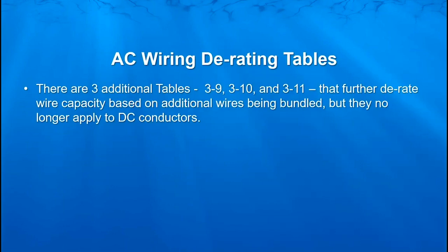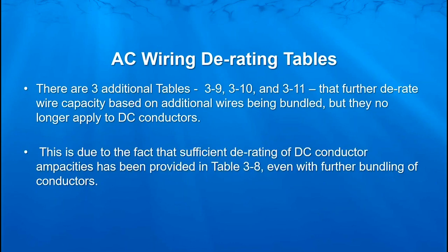There are three additional tables which you don't necessarily have to worry about, just to understand that they're there. They further derate the current-carrying capacity of AC wiring, but they no longer apply to DC conductors. It is felt that there is sufficient derating of our DC conductor ampacities through Table 3-8, which is for three current-carrying conductors, even if we add further wires to that bundle.